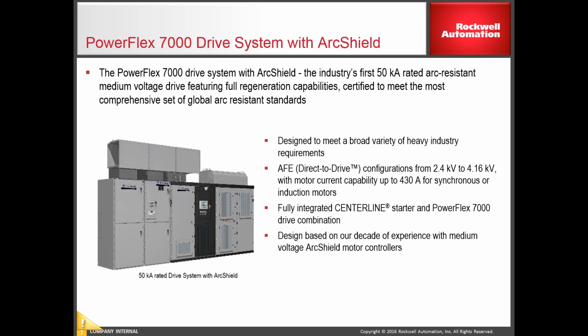So there's two ratings on this drive. There's a 50 kA rating. There's also a 40 kA rating. And in some later slides, I'll show you what the differences are between the two. But this is our active front-end direct-to-drive PowerFlex 7000. So we can do 2400 volts or 4160, up to 430 amps.